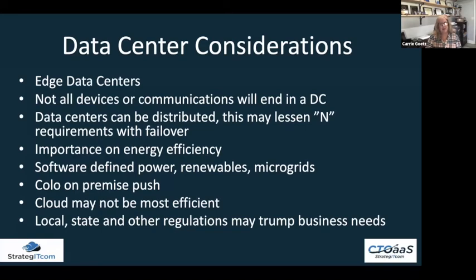And for a long time, we've sort of ignored the IT side of things when we look at building data centers, and it's all about how much power we give to them. But the IT side self-heals. And in many, many applications, it's an automatic failover. And so as we start distributing these edge data centers, if we have an application that's replicated around 10 data centers, we can really save some money and save a lot of the transmission costs because they don't all need multiple transmission paths if the IT load is going to fail over anyway.